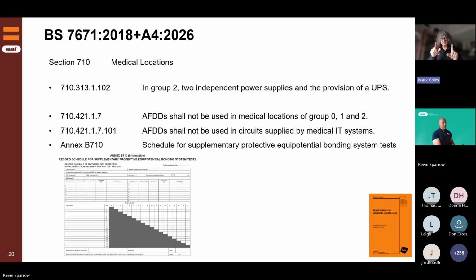So it means that this conductor number one, which goes from there to there, you can see on the diagram, it's all listed in the form here in the schedule. It means you can very quickly look at the schedule, see where it is, and go in and make a test and record the results in the form. It's a basic resistance test, but it ensures that the connections are still there, nothing's happened, hasn't deteriorated, because again, the last thing you want is deterioration in these areas.